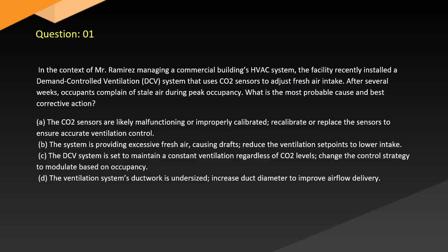A. The CO2 sensors are likely malfunctioning or improperly calibrated. Recalibrate or replace the sensors to ensure accurate ventilation control. B. The system is providing excessive fresh air, causing drafts. Reduce the ventilation set points to lower intake. C. The DCV system is set to maintain constant ventilation regardless of CO2 levels. Change the control strategy to modulate based on occupancy. D. The ventilation's ductwork is undersized. They increase duct diameter to improve airflow delivery.